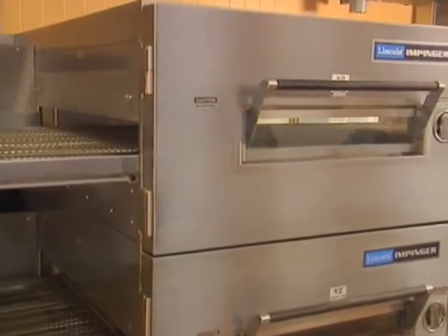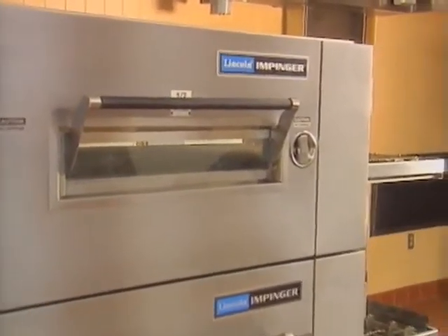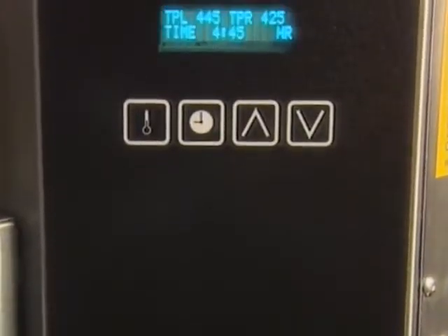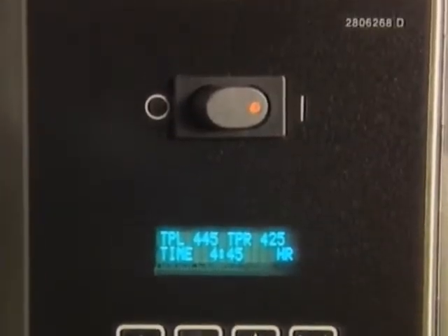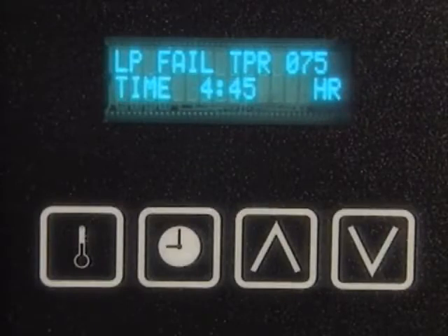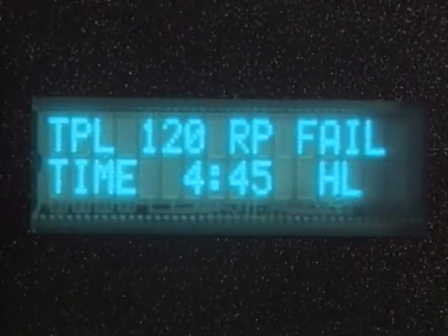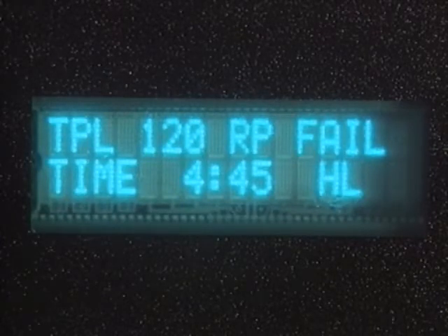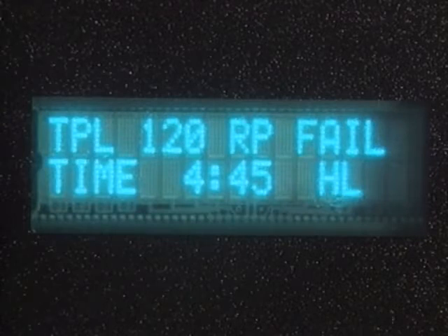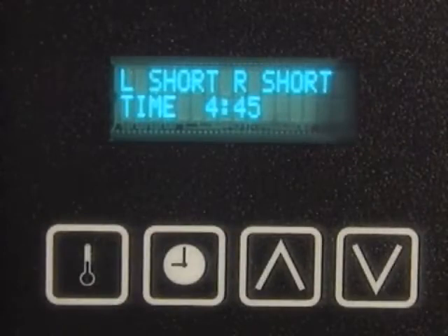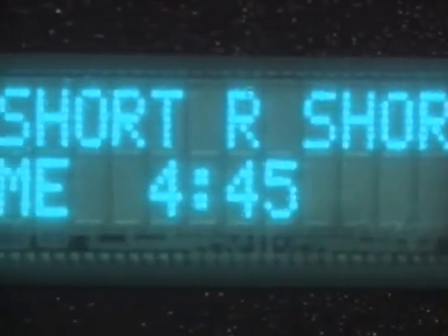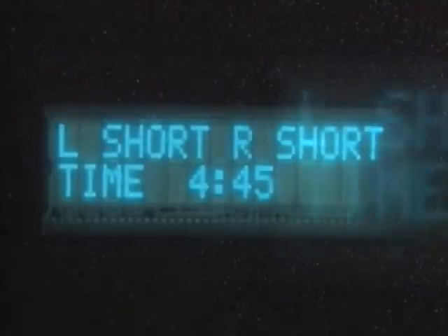Your new Impinger is equipped with 3 diagnostic messages to help you troubleshoot a specific problem yourself, or at least help you narrow it down. The messages you might encounter on the digital display are 1. LP, left probe fail, or RP, right probe fail. This occurs when there's no temperature being sent to the controller from the baking chamber. This generally means a malfunctioning or failed thermoprobe. 2. Shorted probe. This occurs when a constant temperature signal is being sent to the controller from the baking chamber. This will happen if there is no heat being supplied to the oven for some reason.